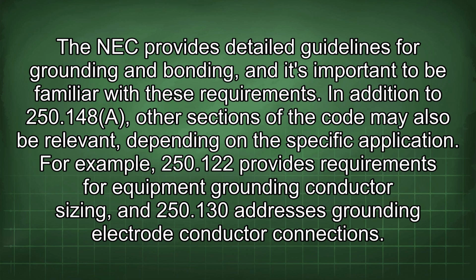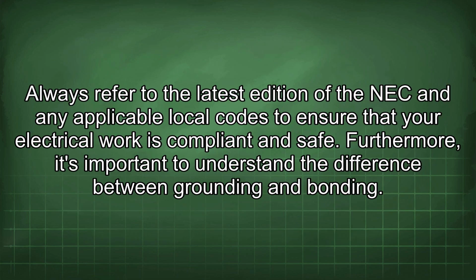In addition to 250.148(A), other sections of the code may also be relevant, depending on the specific application. For example, 250.122 provides requirements for equipment grounding conductor sizing, and 250.130 addresses grounding electrode conductor connections. Always refer to the latest edition of the NEC and any applicable local codes to ensure that your electrical work is compliant and safe.